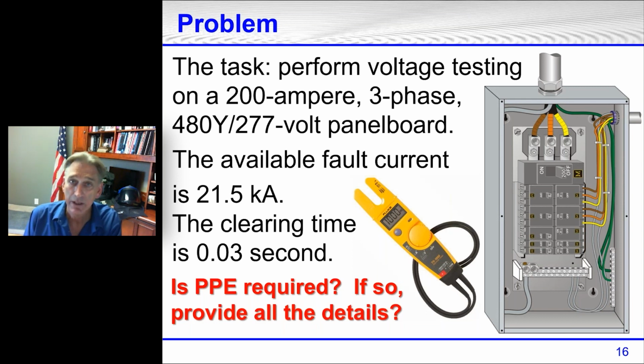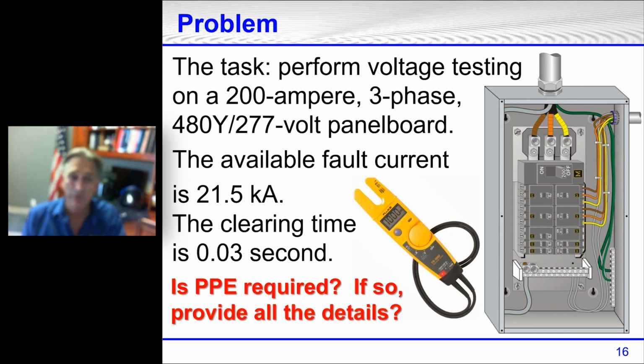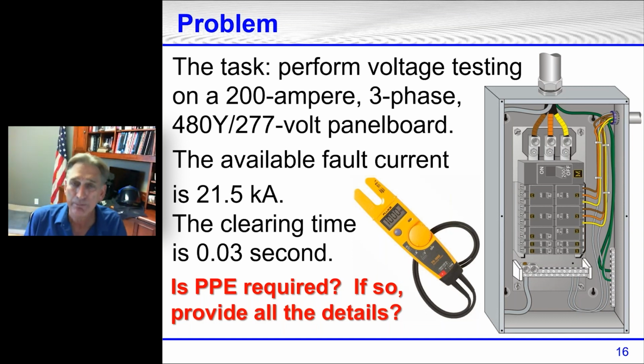It reads current in the jaw at the top. In fact, if you're thinking amp probes, oh, that's got to have a jaw at the top that closes. Well, this one doesn't have to close. So it reads voltage and it reads current, but it also reads voltage through that jaw at the top, through that opening at the top, without using leads. And so this particular voltage detector, this test instrument, will read voltage and current at the same time.